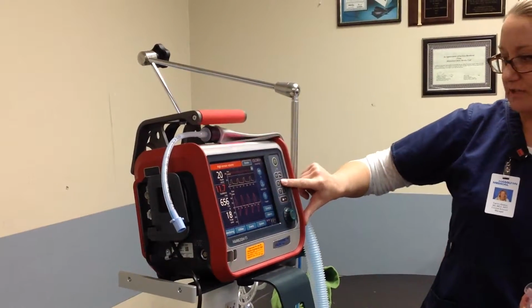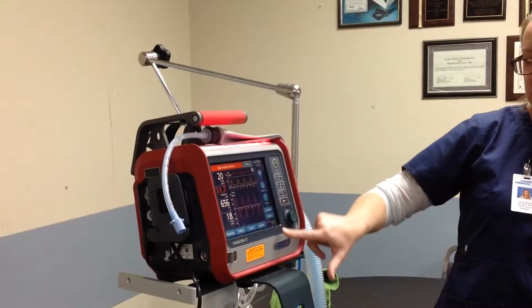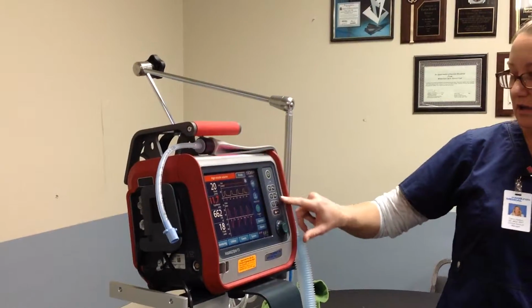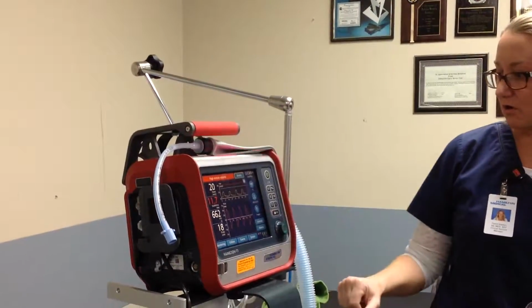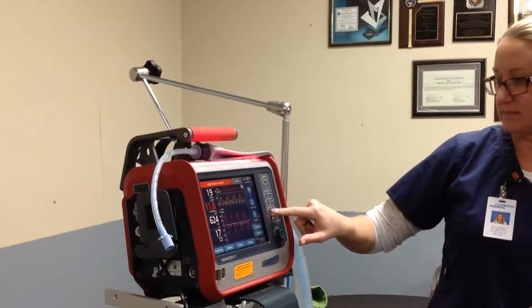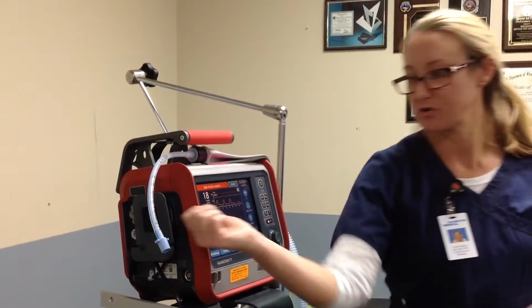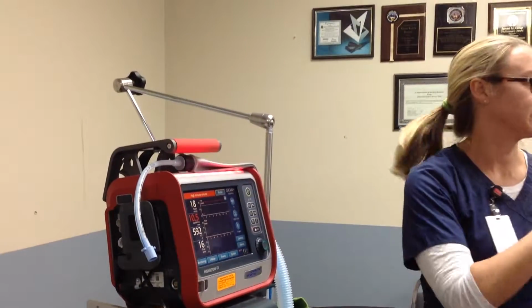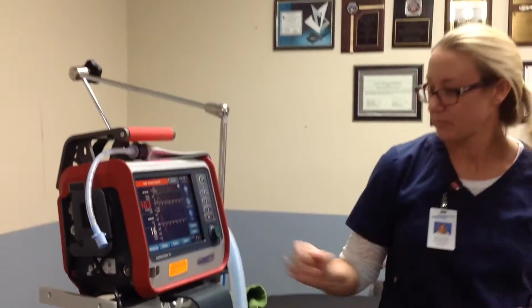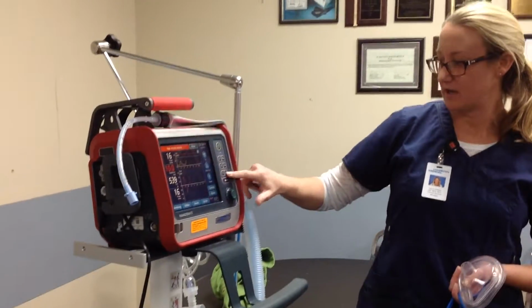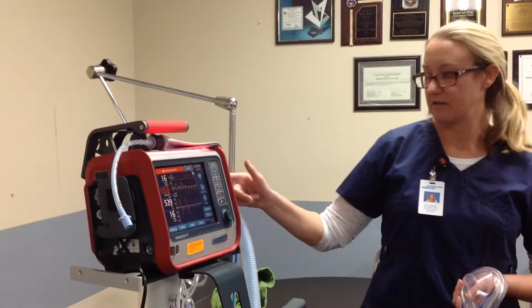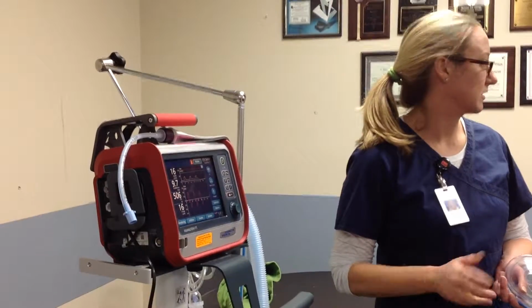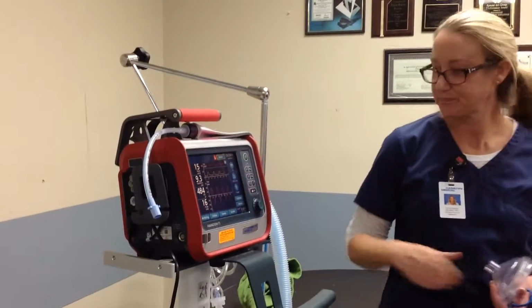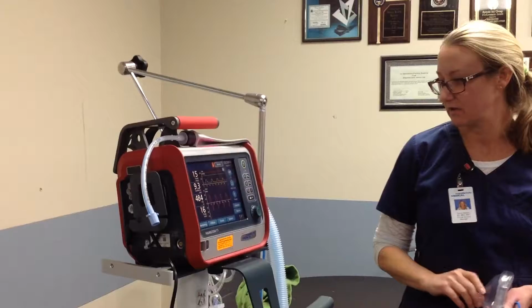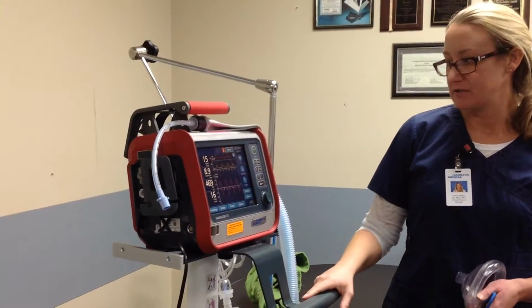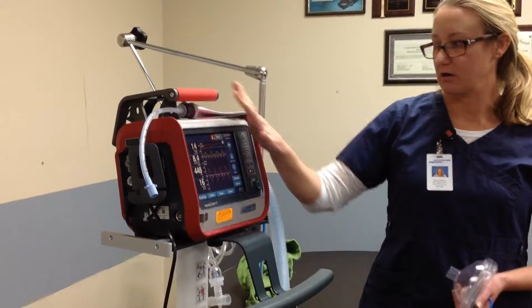Cancel that. Increase oxygen, that's just going to take you to 100% oxygen for 2 minutes, and it tells you that. Turn it off, and it takes me back down because we don't want it to alarm. This print screen, it looks like a printer. If you put a thumb drive in here, you could do screenshots and send them to us if you ever have anything that you're trying to troubleshoot. And it looks like a spray paint can here. This is how you turn on the flow meter that drives the nebulizer. I don't know if you guys have used that function at all, but I'll turn it off so it doesn't holler at us.